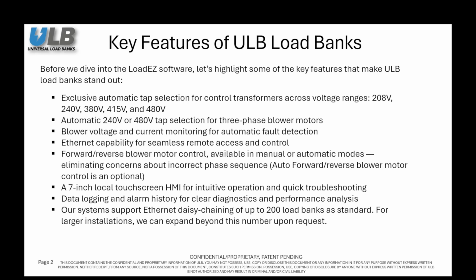For added convenience, forward and reverse blower motor control is available in both manual and automatic modes, eliminating any concern about incorrect phase sequence. Automatic mode is optional. Each unit includes a 7-inch local touchscreen HMI for intuitive operation and fast troubleshooting. And finally, comprehensive data logging and alarm history provide clear diagnostics and help with performance analysis. Our systems support Ethernet daisy chaining of up to 200 load banks as standard. For larger installations, we can expand beyond this number upon request.